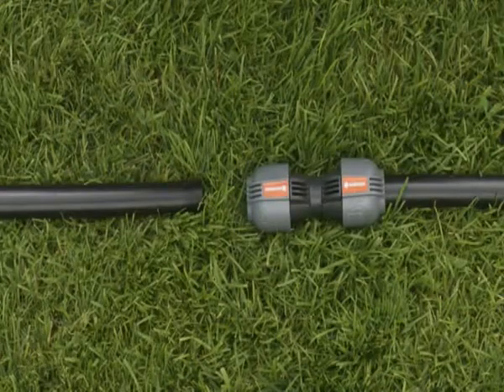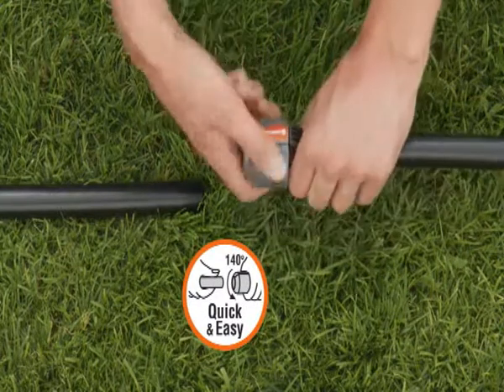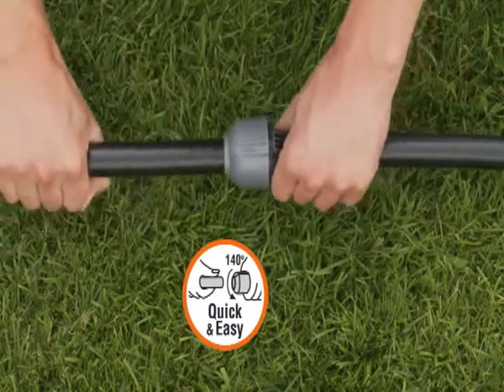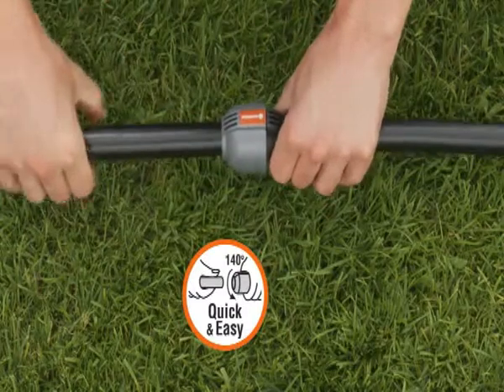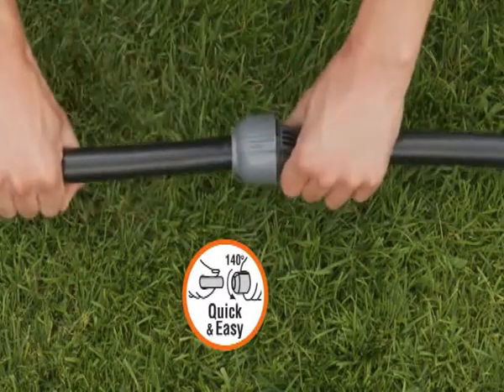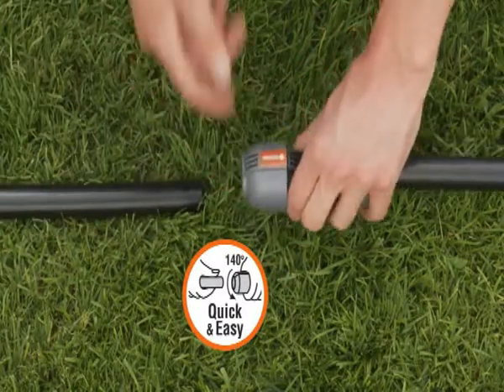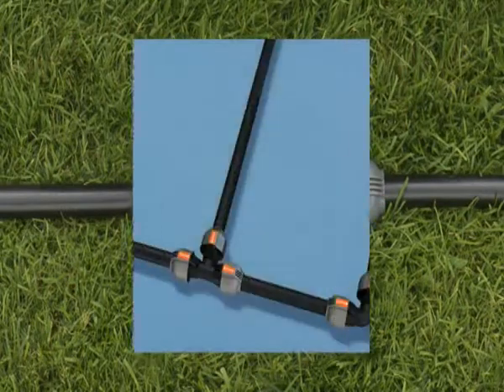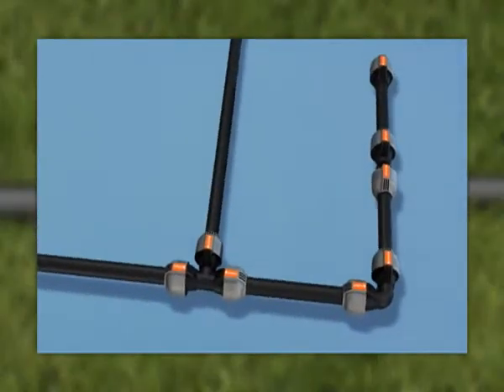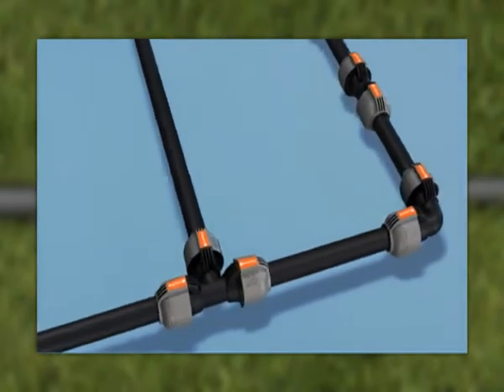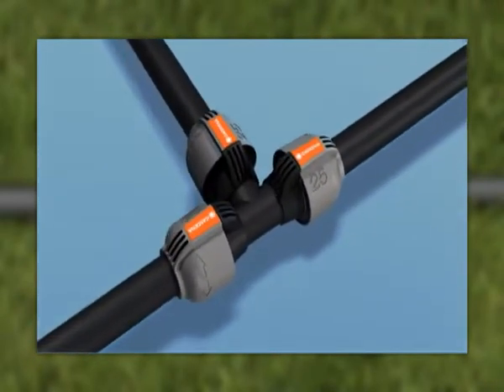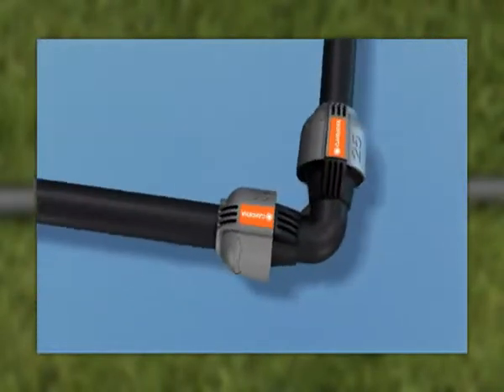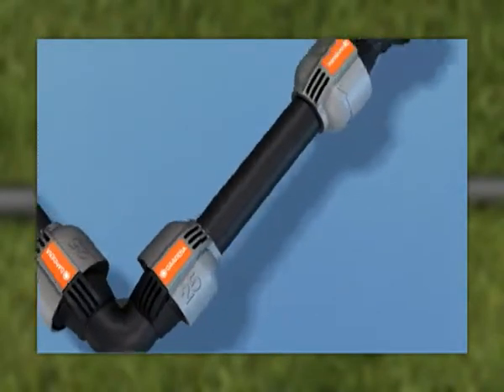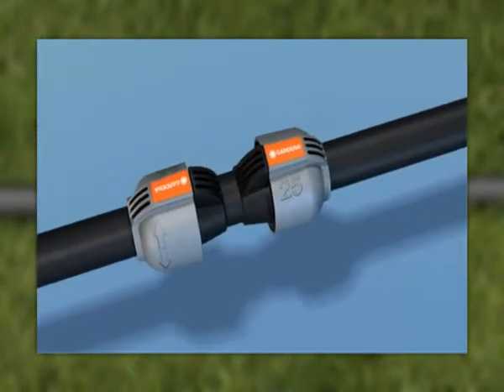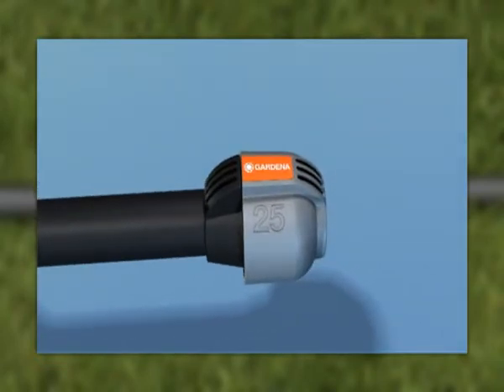A special feature of the joints and connectors is the unique quick and easy simple connection technology. You can ensure a pressure-proof joint or disconnect again simply by turning the connector 140 degrees. For connecting the pipes, a variety of fittings are available. For pipe branches, there are T-pieces. For changes of direction, L-joints. For extending lines, there are straight connectors. And to close a line, end pieces.